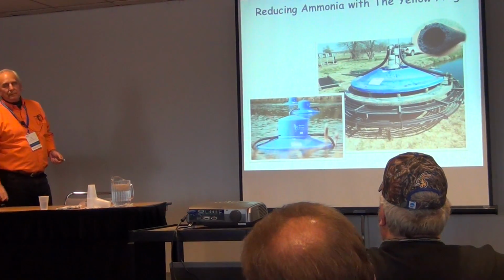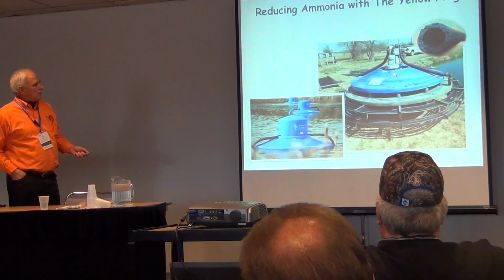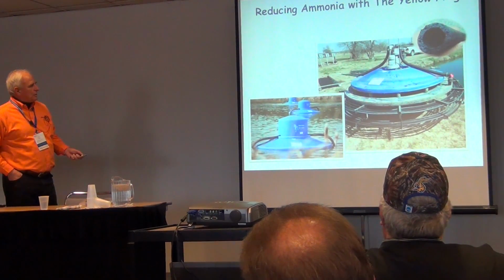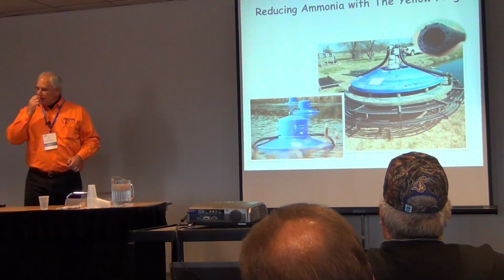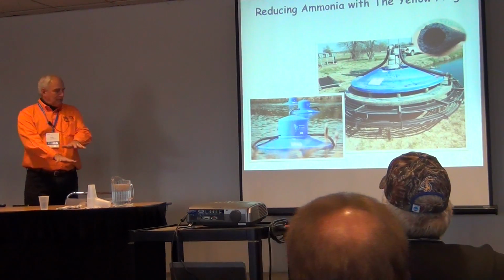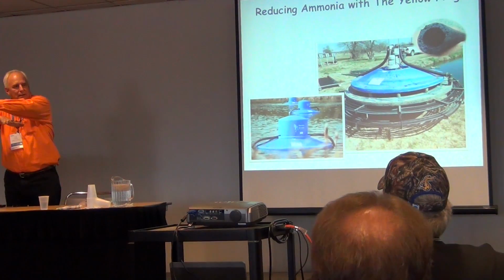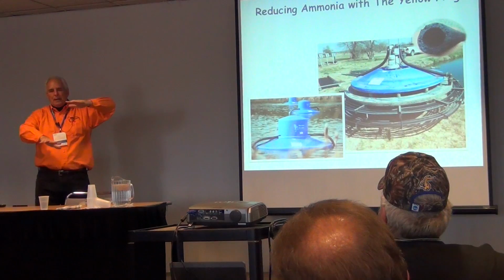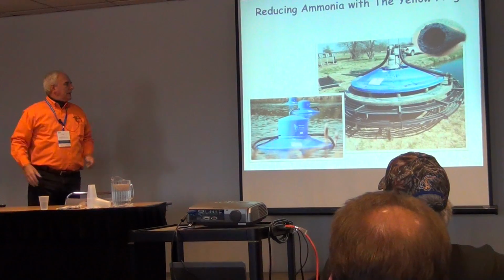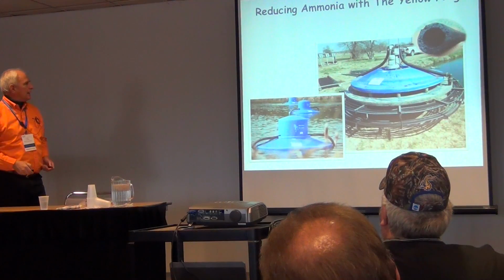Now, you also have to get rid of ammonia. So this is an aerator. We bolt a 1 1/4 horsepower blower to the gear reducer, and we put the air out through 2 headers, and it goes into 4 concentric rings that are staggered of good aeration hose. And so now the bubbles rise up, but they rise up into 7 million gallons a day going horizontal. So to get your detention time, the bubbles go like this. And so now I get my detention time horizontally and not vertically. So you can see one floating here.